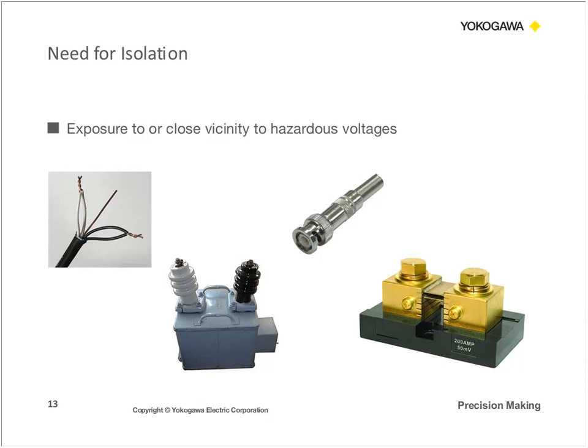So as a general rule of thumb, you want to make sure that you perform all connections with all the devices disconnected from the mains. So this means whether this is a motor under test or if this is an entire test system, you want to make sure that it's not connected to the line power. And once you have done that, then you can make all the physical connections and wiring that you need to before you begin measurements.